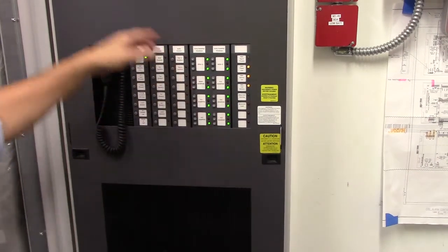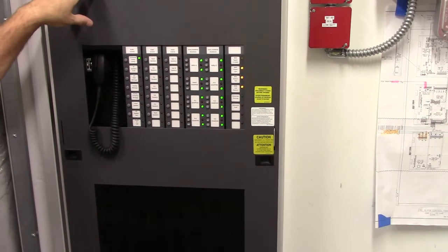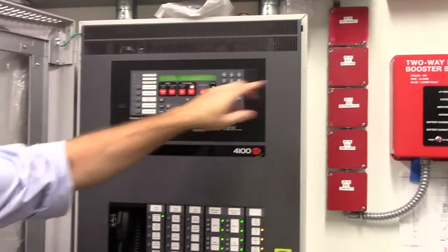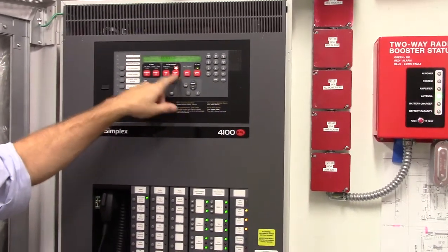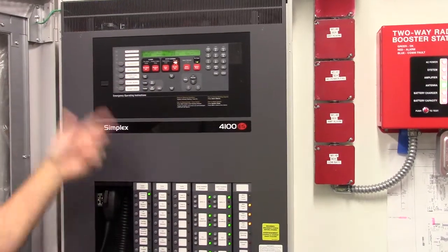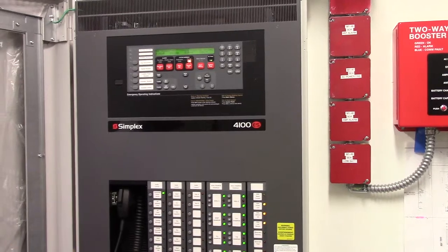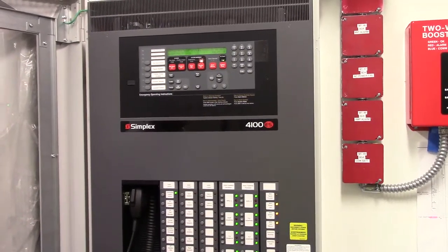Speaking of the troubles, the specs on this panel required this panel to have a resound. So any active conditions like these troubles that are on here right now for the BDA, every 18 hours these will re-ring in as a trouble. Same thing with fires, everything else. If the condition stays on there, it will resound the signals, whatever. But I mean, it's a dorm, so if it's sitting on there for 18 hours, it's something bigger going on anyways.